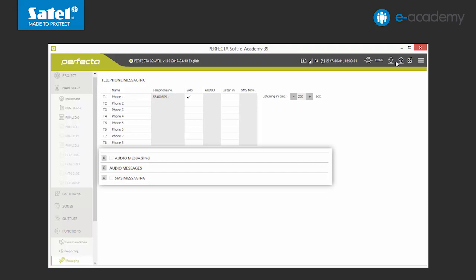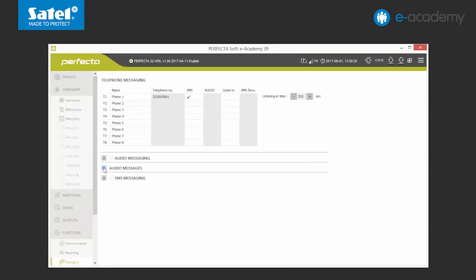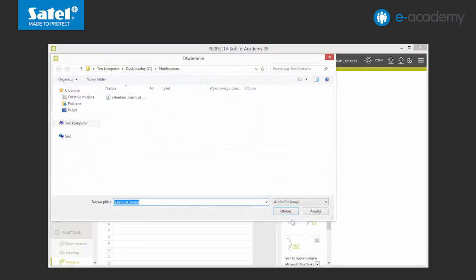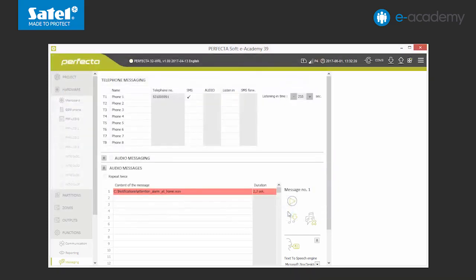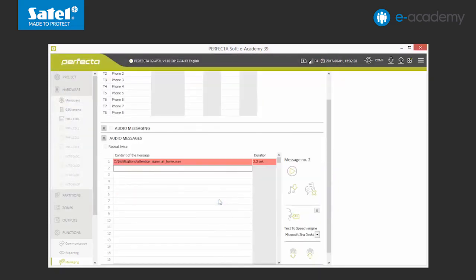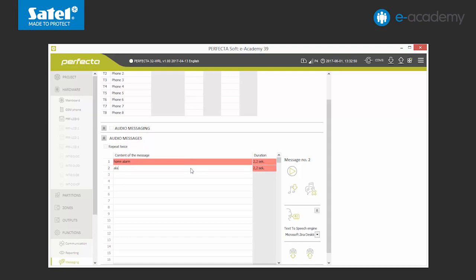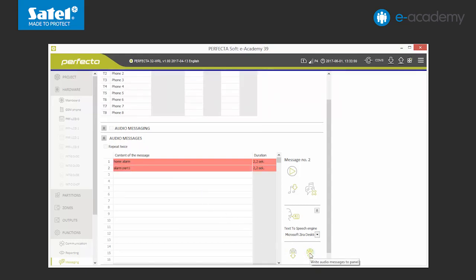Under the phone number chart, you can see the list of audio and SMS notification settings. First, we will move on to audio messages. We have 16 messages to choose from. We can also use WAV files recorded from the computer, or enter the message and use the speech synthesizer installed additionally on the computer. In order to make it easier to differentiate between them, we can give them shorter names. After setting the messages, send them to the control panel. This is done differently than in case of other system parameters. You have to use the button visible next to the list.